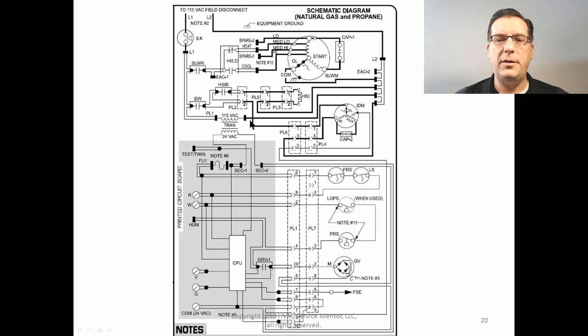Here we are backwards. Comes from a Molex plug, PL2. And PL2 is going to be on the control board. Comes from IDR, induced draft relay, on that control board. So check this out. Here is 24 volts at the L1 terminal, or I'm sorry, 120 volts at the L1 terminal. It goes on the board and it is sitting and waiting.